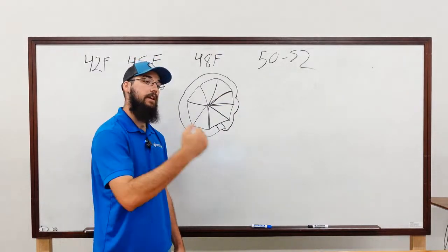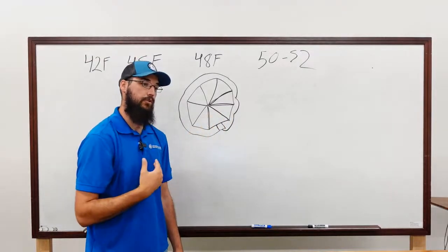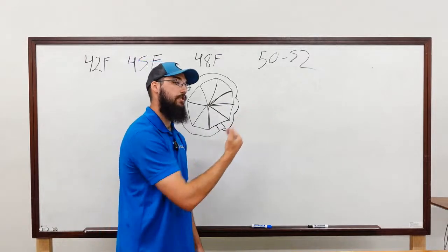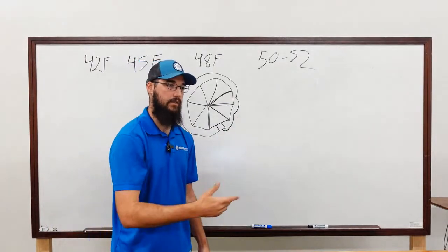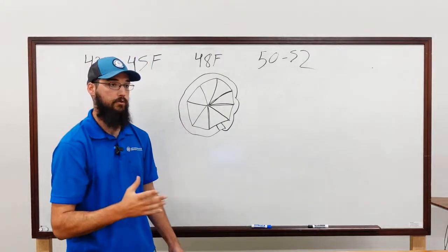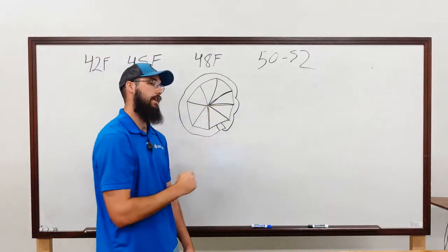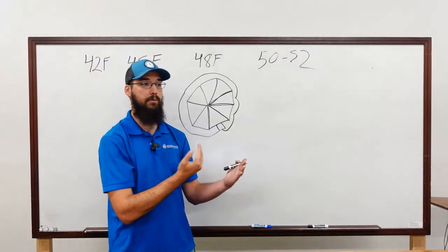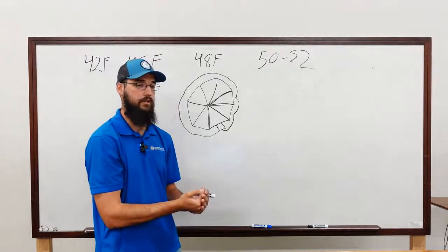If you're having issues with a chiller surging, or you're trying to keep it from going into a surge, a trick you can do is run your current limiter down. Set it down, whatever you decide, 60%, 50%, you choose, but lower your current limit, and that's going to force these vanes to close, and it's going to help you prevent your machine from pushing itself into a surge condition.